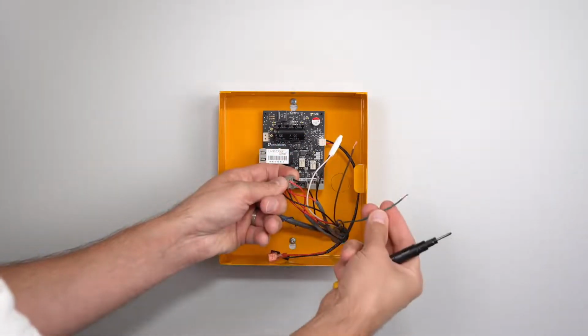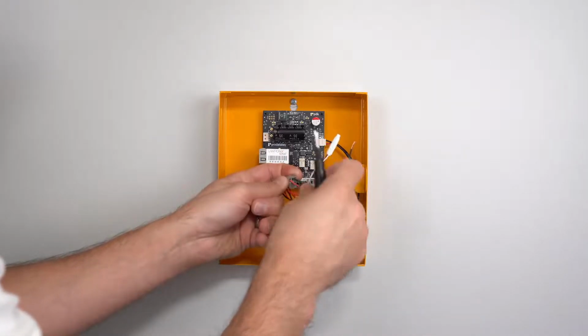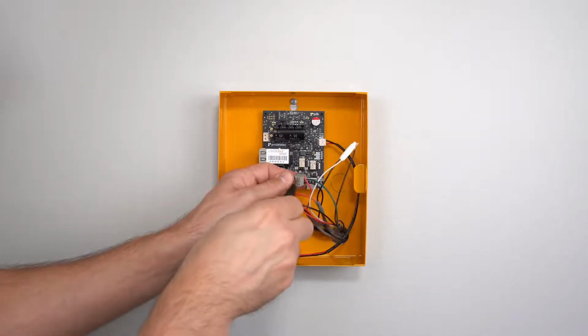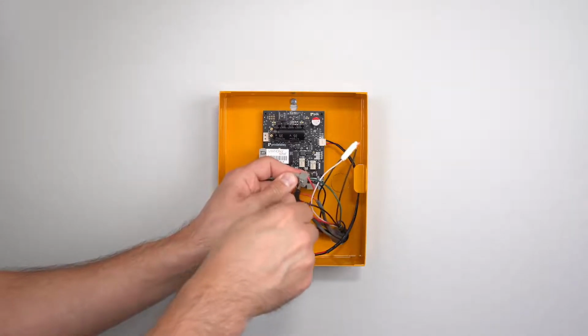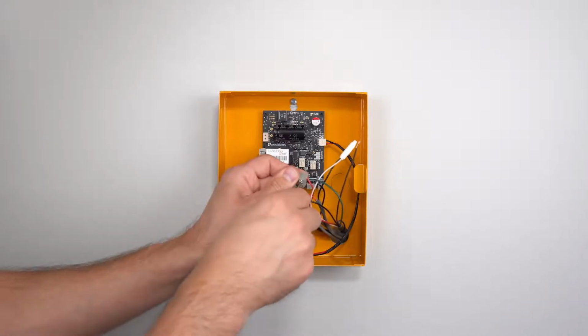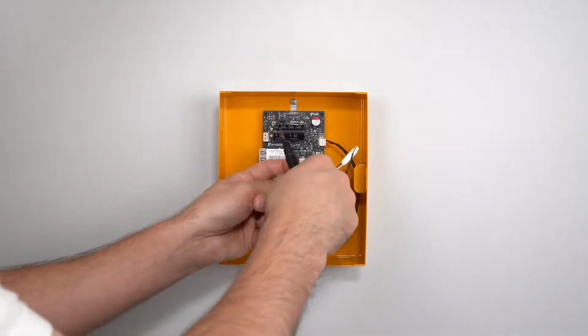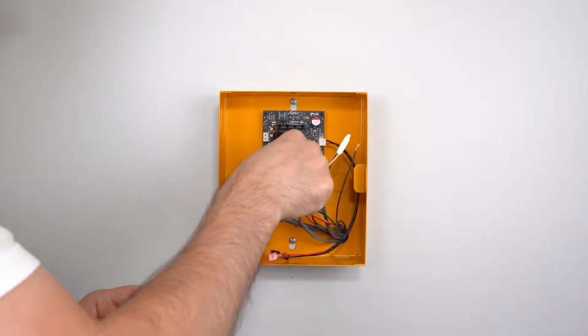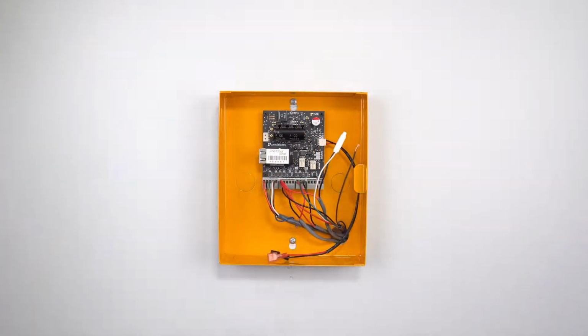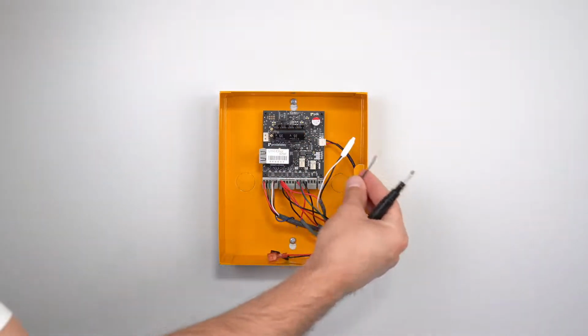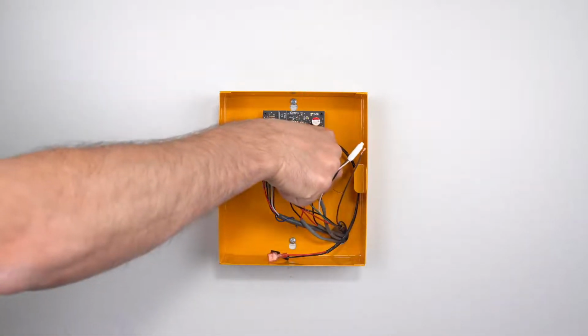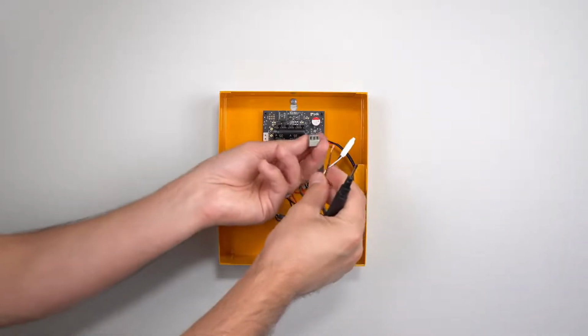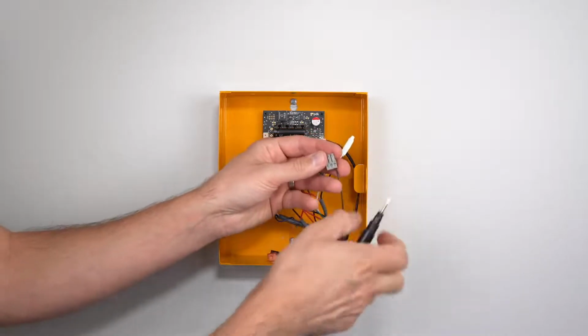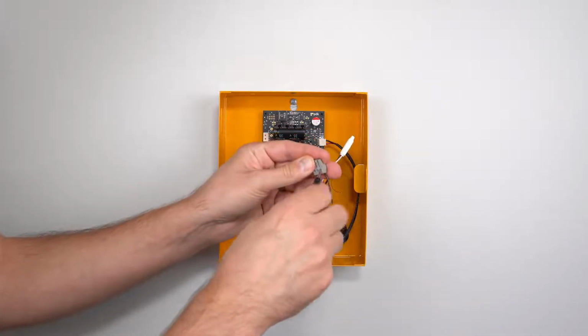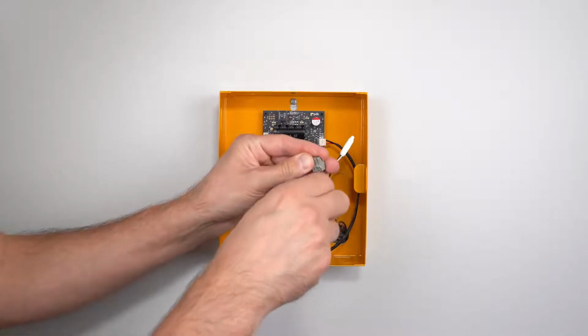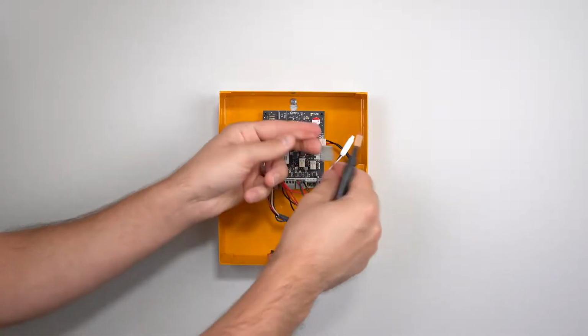And you'll see this in our quick start guide. Now the other wire that I'm connecting right here is the normally open wire, and that's being connected to the Rex trigger input. So in other words, when that Rex triggers, it's going to get a ground loop that comes through and lets the board know that that Rex was triggered. So I can get a forced door open if I want to utilize that feature. And then you'll see the normally closed wire, which is this black wire, is going to go into the normally closed on the Rex coming into the normally closed on the door controller. So you're just making this ground loop all the way around.